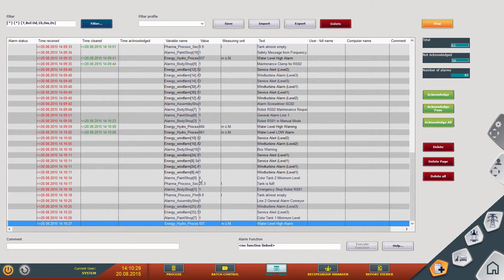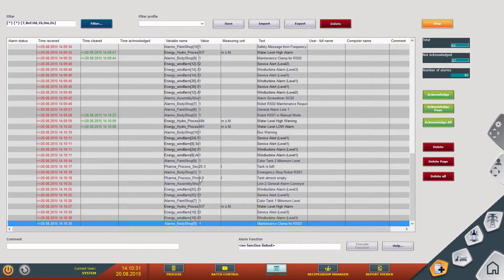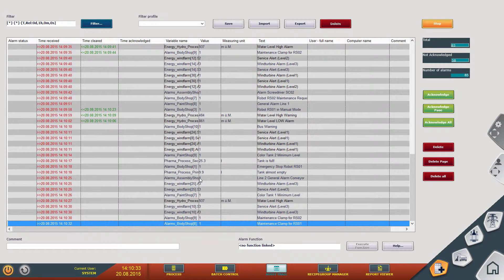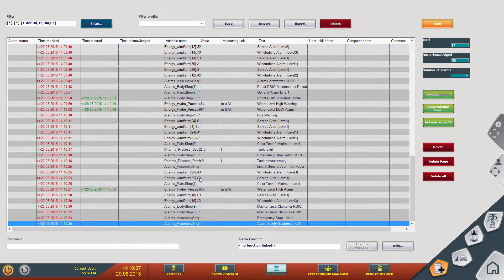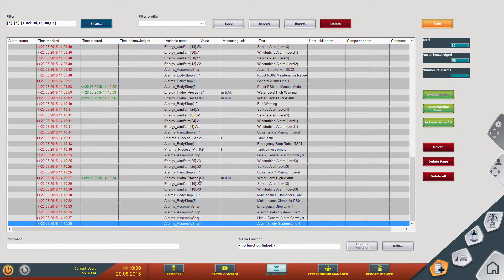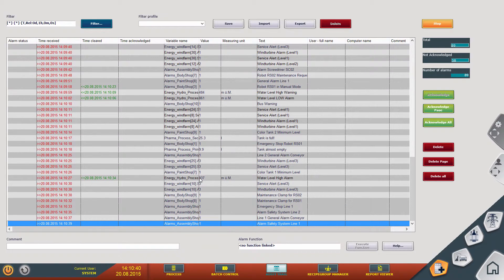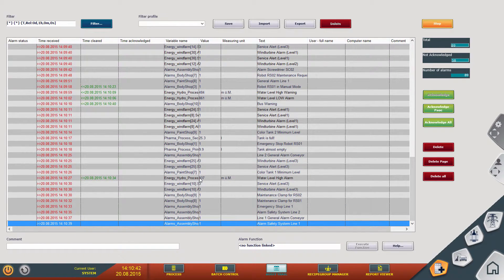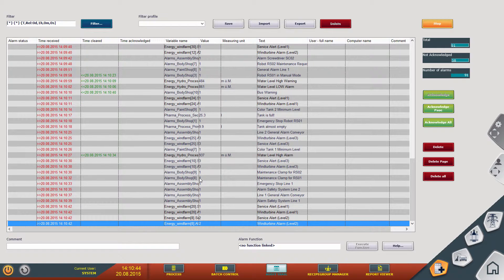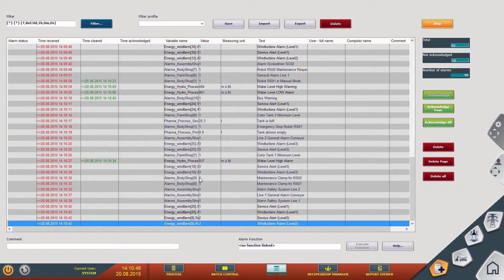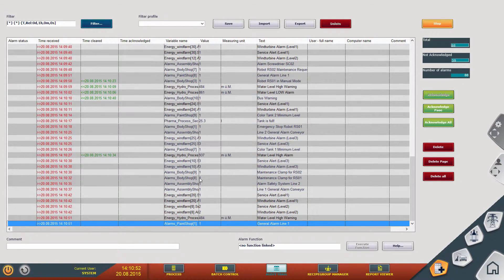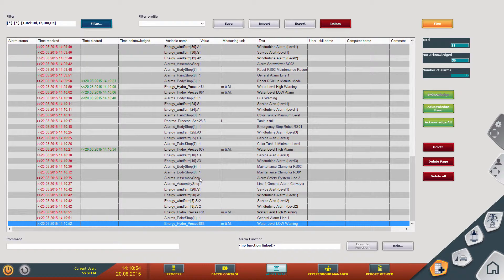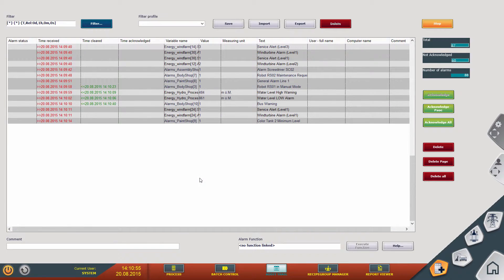This covers target value requirements as well as recipes and changes to archive entries. The following is noted in the protocol: which documents have changed, the old and the new value, date and time of change, the user, the computer on which the change was made, and the signature for signed actions. In addition, a comment on each entry can be saved in this way.